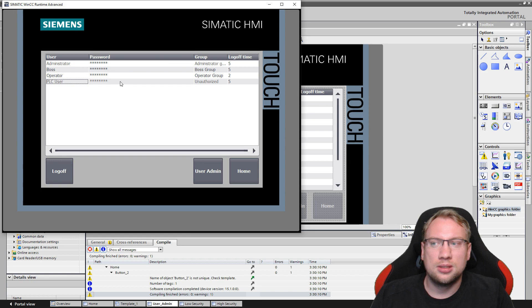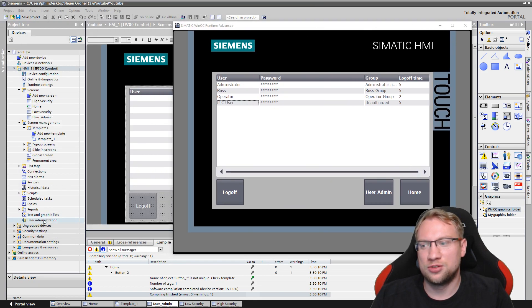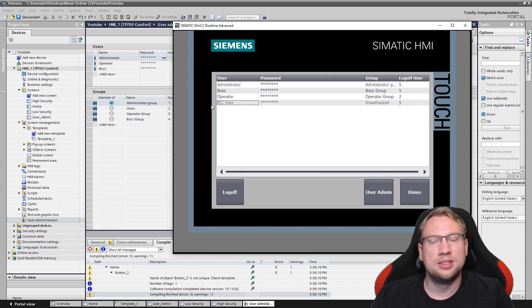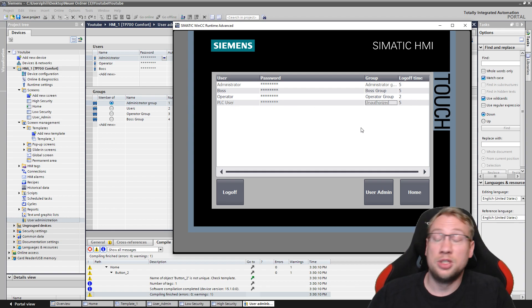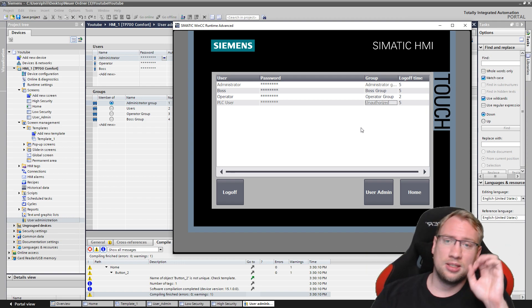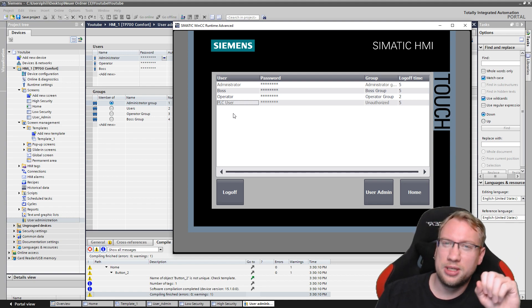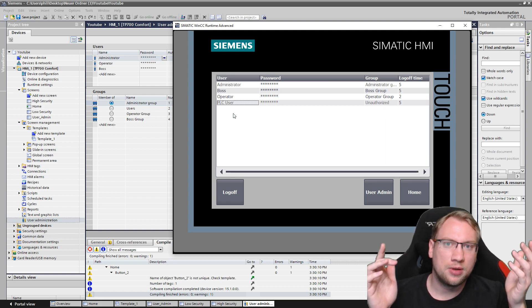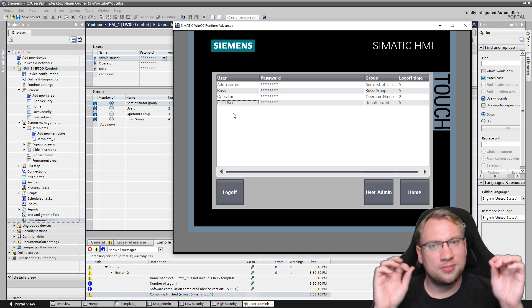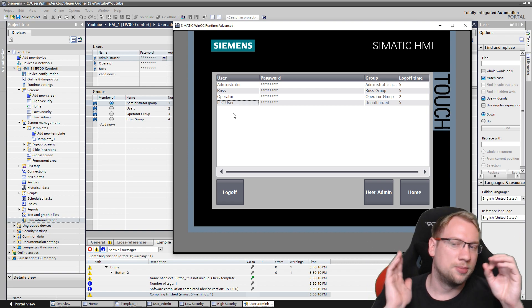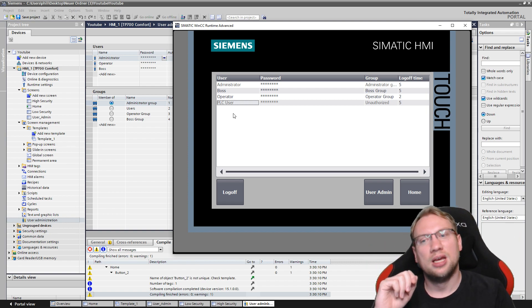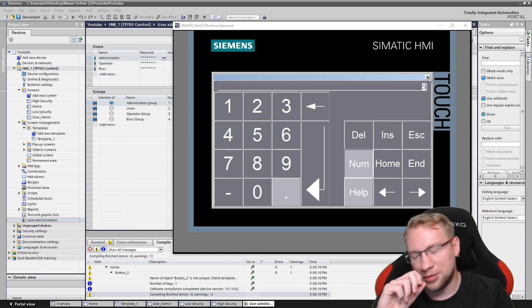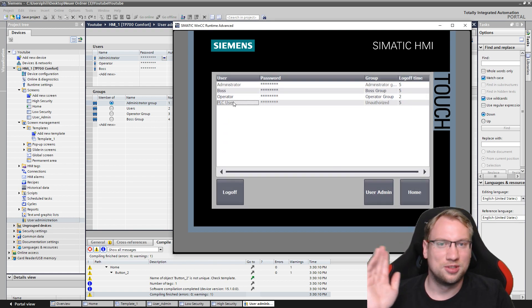There's one more user not shown in TIA portal's user administration — we only have administrator, operator, and boss there — but here on the HMI there's also the PLC user. This PLC user is important for communication between the PLC and WinCC or the HMI. Without that user they couldn't communicate; it handles data transfer between the two. Even as administrator, you cannot change anything for the PLC user except the log off time, which doesn't really matter because the PLC takes care of it.